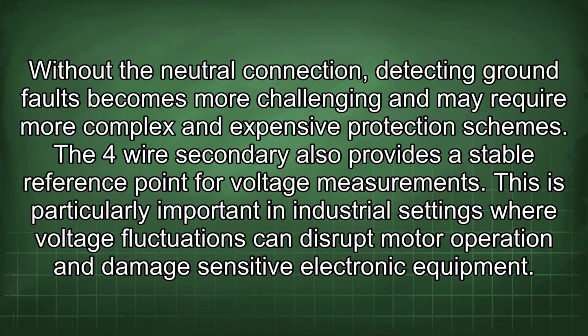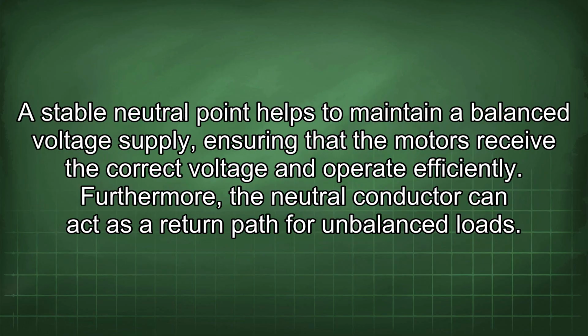The 4-wire secondary also provides a stable reference point for voltage measurements. This is particularly important in industrial settings where voltage fluctuations can disrupt motor operation and damage sensitive electronic equipment. A stable neutral point helps to maintain a balanced voltage supply, ensuring that the motors receive the correct voltage and operate efficiently. Furthermore, the neutral conductor can act as a return path for unbalanced loads.